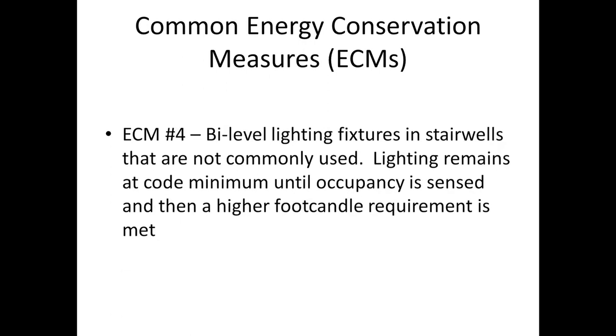Bi-level lighting fixtures, this is big, especially when you get a high-rise when there's very few people that take the stairs. Building codes require that you have a certain lighting level present at all times in the stairwell. A lot of times the power density, the amount of watts per square foot of this lighting, is a lot more than it needs to be. We can install fixtures that dim down to a minimal code requirement when there's no occupancy, and then brighten up to comfortable lighting conditions when someone enters the stairwell.